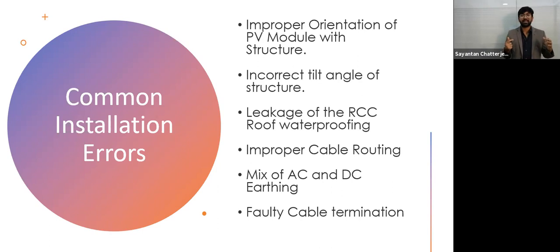And the next one is the tilt angle of the structure. If the tilt angle is different, like for any place where the requirement is 23° and we are putting it at 35° or 5°, it will be hampered. The generation will decrease. But in the case of a tilted rooftop, obviously the tilt is with the roof itself. In that case, we have to calculate the loss of energy due to this tilt angle, and that should be incorporated in our financial modeling. Otherwise, that will show a very rosy picture. After installing the solar power plant, after 1 year, we'll get the real picture of what the plant should have generated and what it is generating.